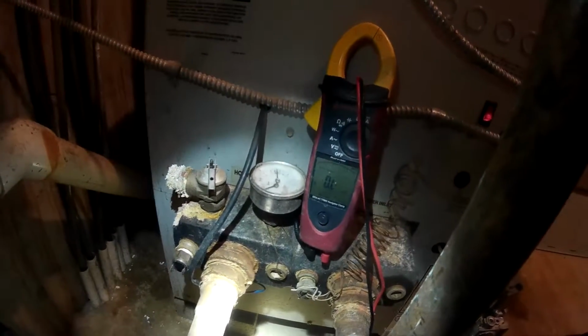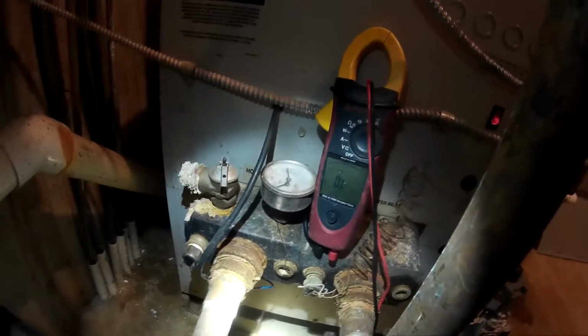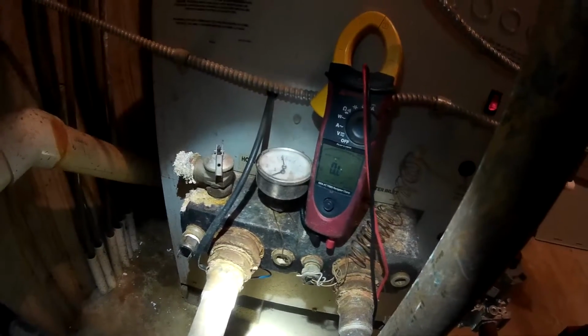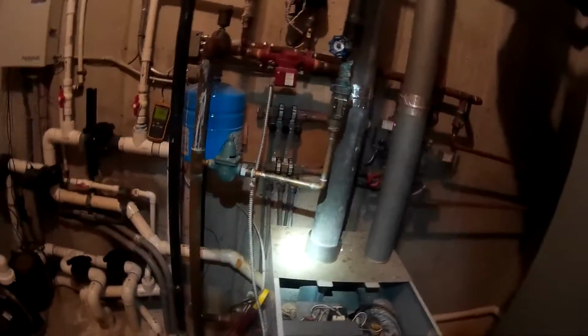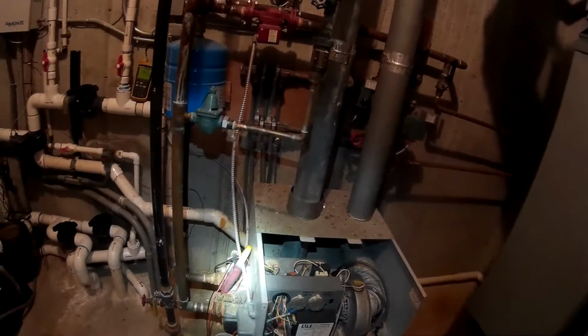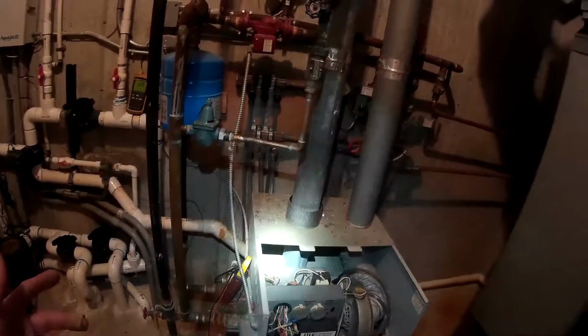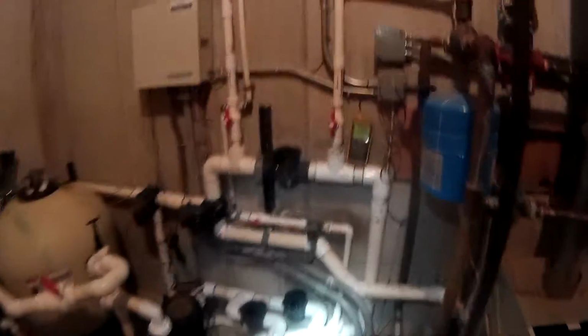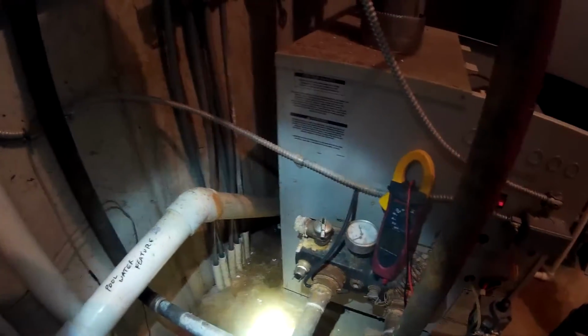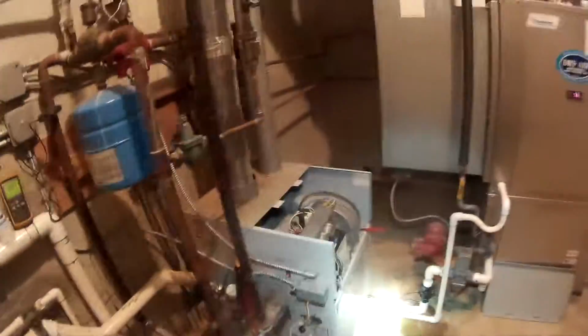So my operating control and my high fire control go into here, into the manifold. One thing I do got to check is, okay, it does go into the manifold. We're on well water. One thing that might be going on is that immersion well could have buildup on it, insulating the probe. So that might be one factor. But I am going to order an operator, just to be on the safe side. You really don't want to screw around with overheating the boiler or overheating the pipes. And another thing is this T&P valve. It's really crusty. So, that's a safety device that's got to be repaired. So we're going to get that fixed.